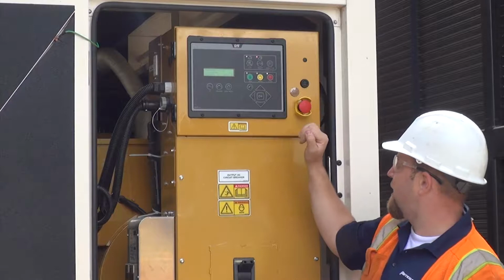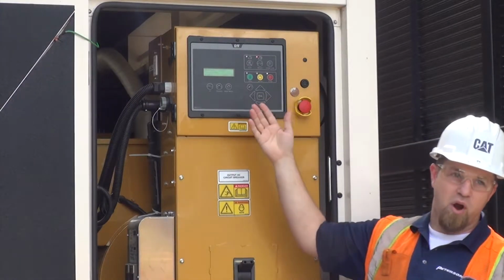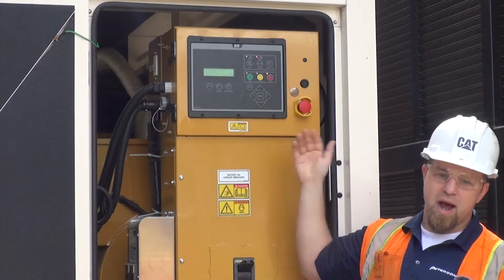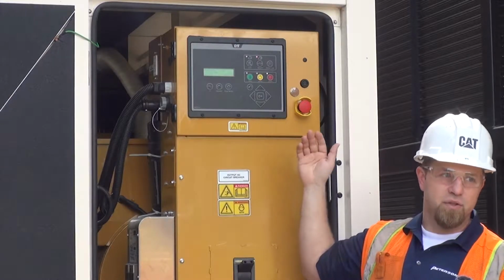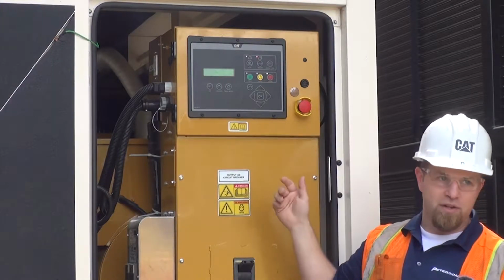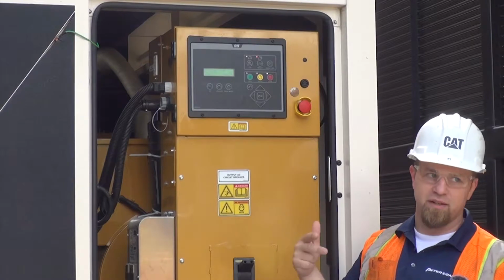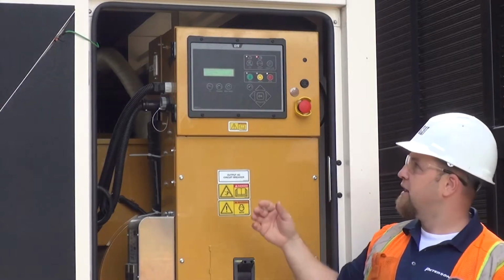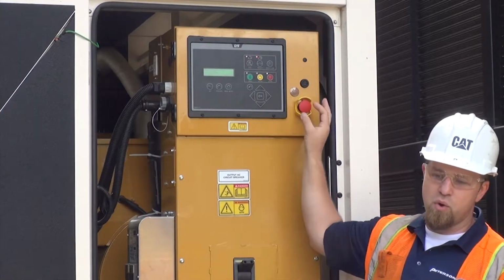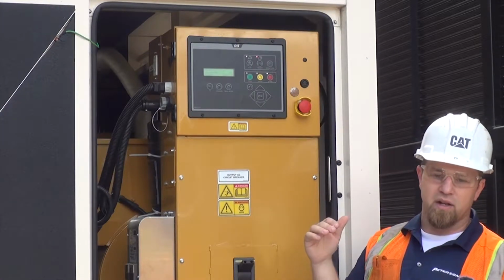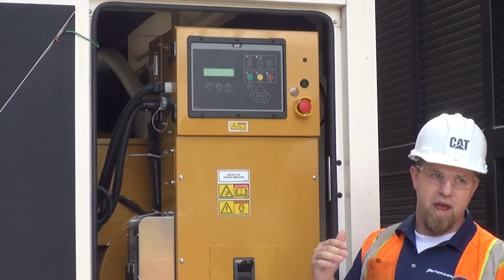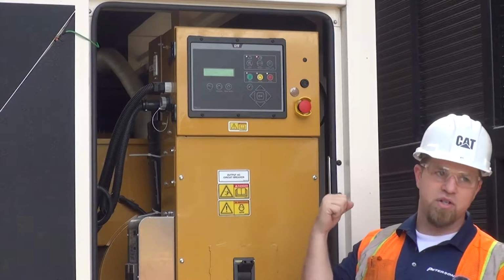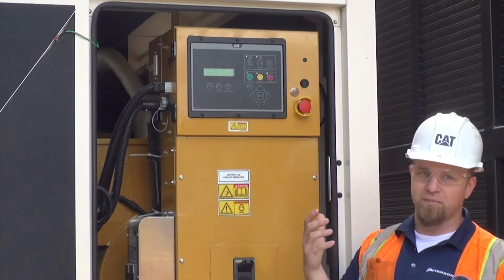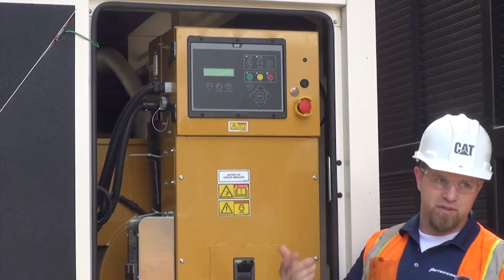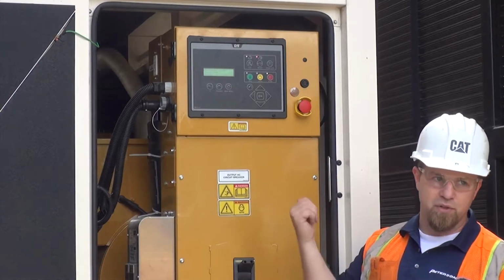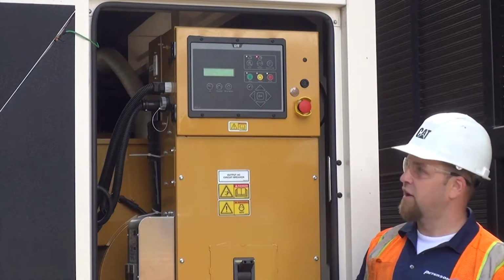So always make sure you put it in stop before you try to reset something. With the e-stop, I showed you what a hard shutdown is. I would not recommend using that unless it's truly an emergency—you're hearing knocking noises, seeing flames, something horrific. The reasoning is that it has no cool down to let the turbo spool down and the oil settle. You are hard shutting that thing down, and you'll end up damaging seals, turbos, things like that. You'll go through them real quick if you're using that all the time to shut things off.